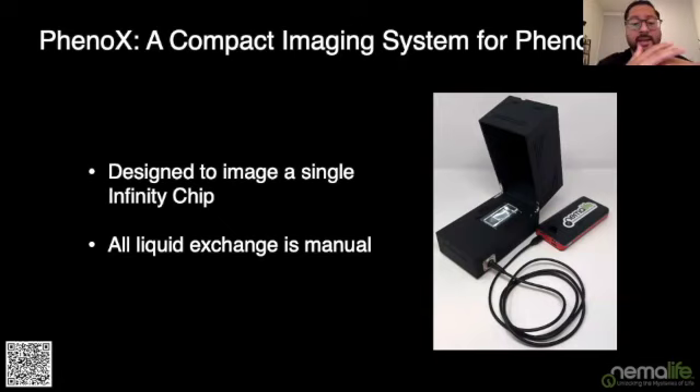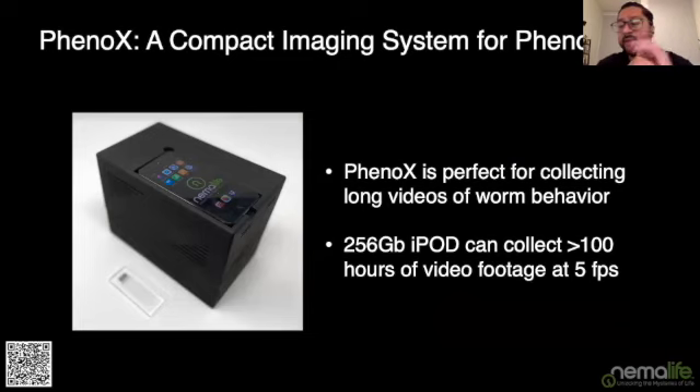The PhenoX is only designed to image a single chip at a time, and because we've shrunk the form factor, it doesn't include pumps and programmable controllers for automated liquid exchange — liquid exchange is manual via syringe. However, if you're using a 256 gigabyte iPod, you can collect 100 hours of video footage recording at five frames per second. So if you're doing a stress or behavior assay that takes multiple hours, the PhenoX is perfect for that.